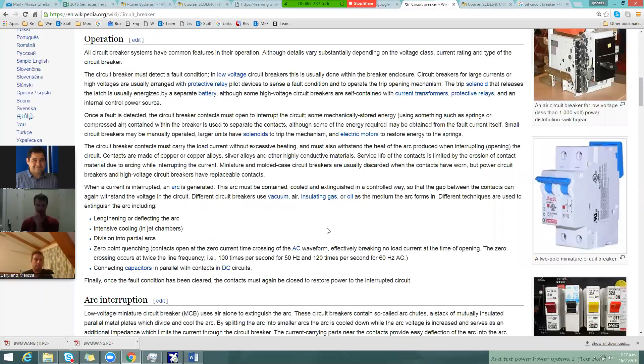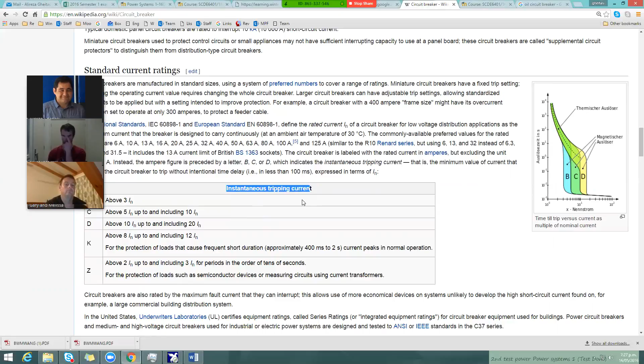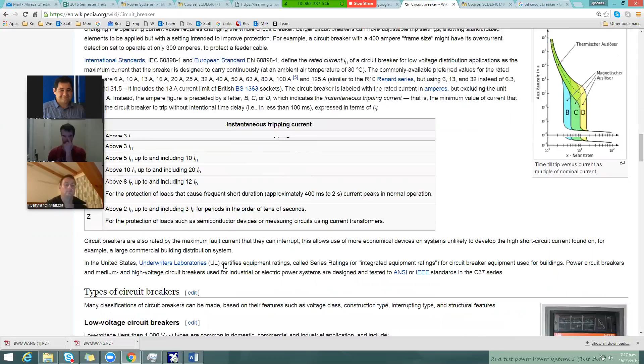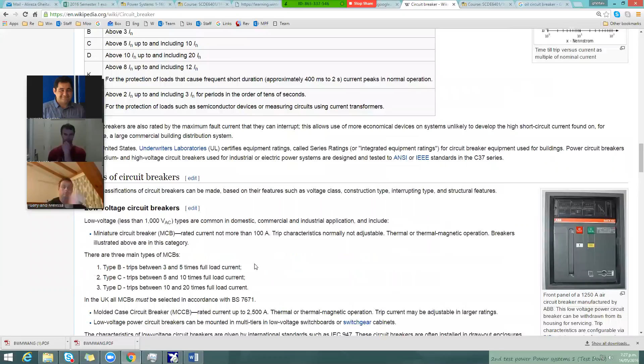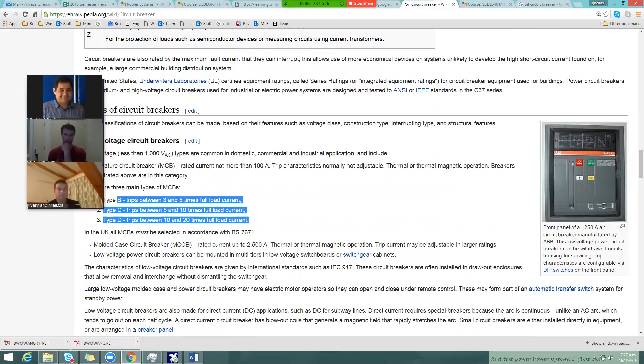For all circuit breakers we have an area - a discussion about in which situation they are capable of instantaneous operation. This is more for MCBs, so we end up with these zones. But looking at types of circuit breakers, we have different types - this is just about MCBs, usually less than 1000 volt AC. We have type B, type C, and type D.